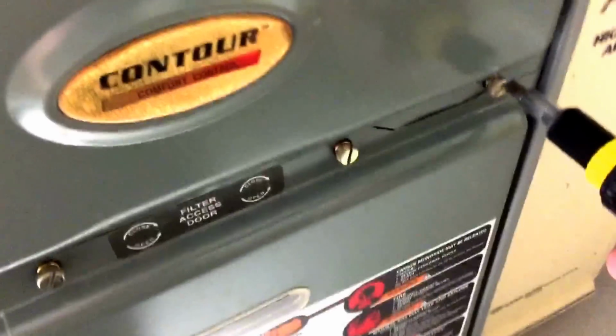I see so many return boots and filters where there's a huge gap. So all you're doing is sucking in air from wherever it's located, a basement, crawl space, or closet, sucking in air after the filter so it's not getting filtered, and all that dirt winds up going into your furnace.